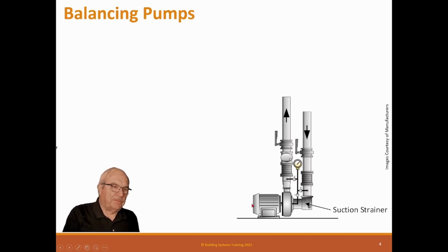They do make base-mounted pumps and inline pumps and many pumps that look different, but they're mainly all centrifugal pumps that we deal with. This has a suction pipe that comes down, and this particular one has a suction strainer. Your job may not have a suction strainer here. It may have a regular Y strainer up here that has a Y down this way, and it may have an elbow here. If it does have an elbow and it needs a transition because it's a different size, it must be flat on the top and slanted on the bottom. The reason for that is, if you put a bell mouth on there, it could entrain air bubbles and cause cavitation of the pump. So best practice is it's flat on the top.